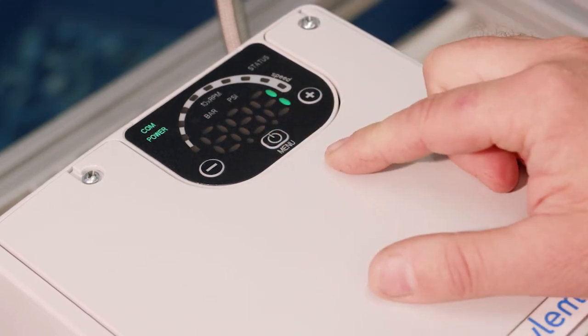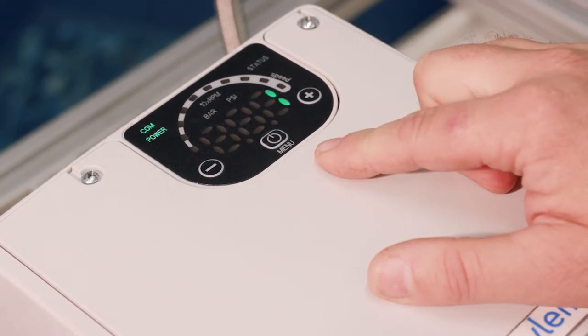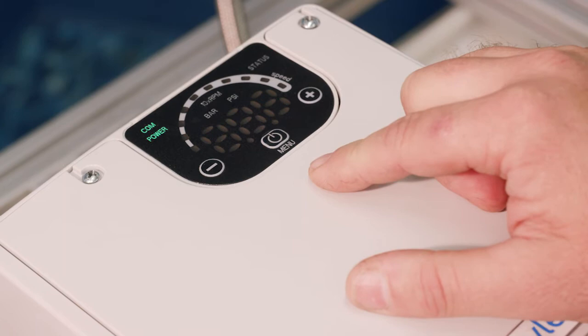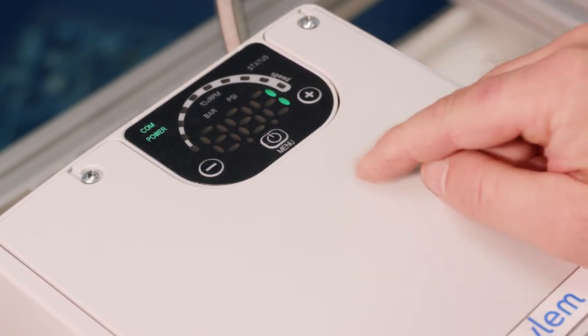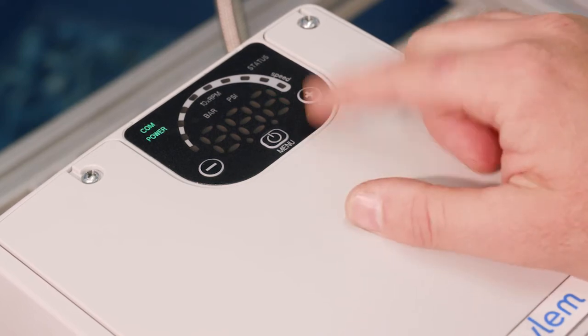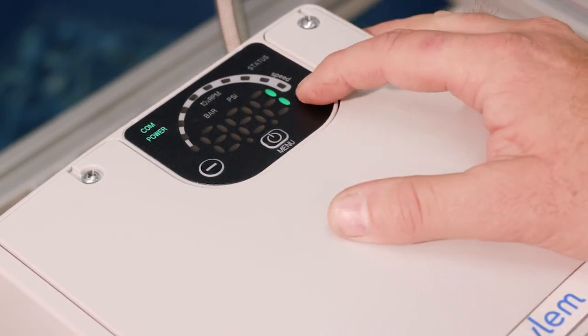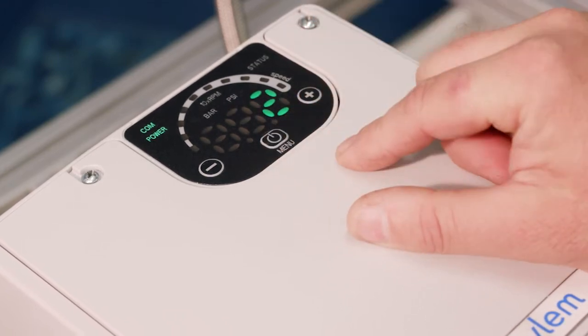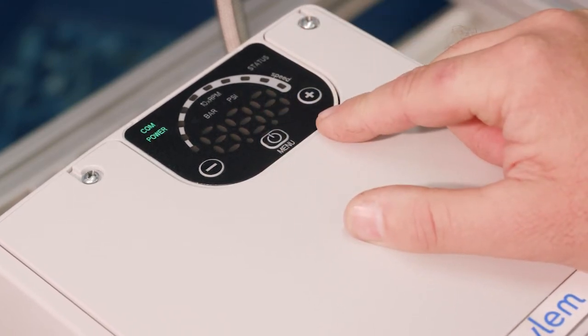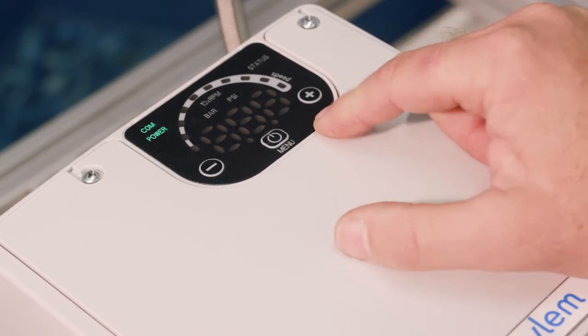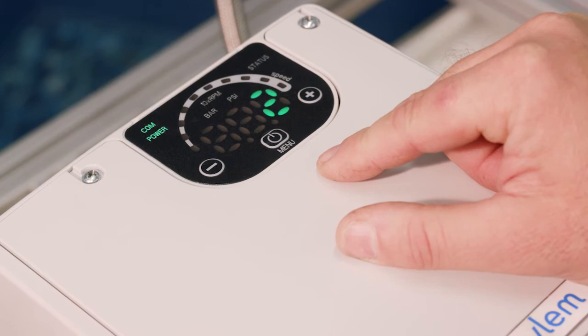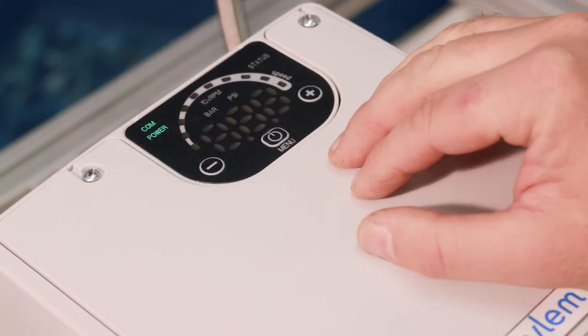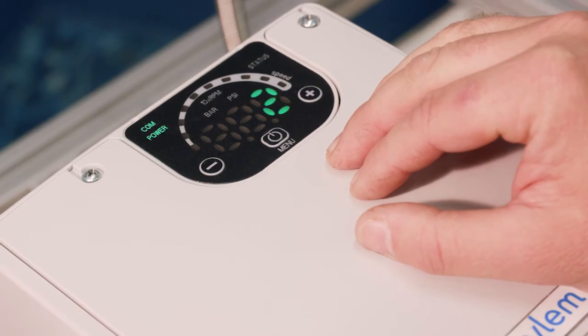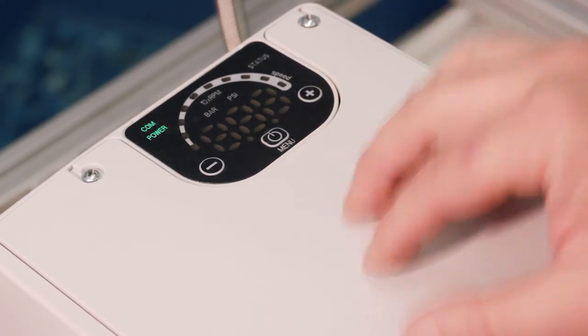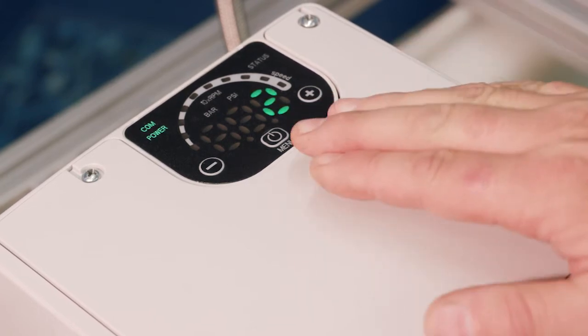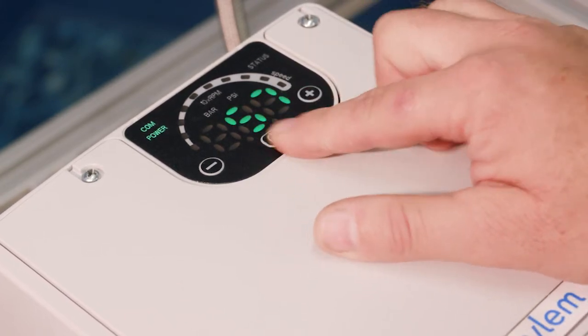And 55 says your address, right? So one thing that we have to do is identify pump 1 versus pump 2. So we'll call this pump 1. So we're good there. 56 is how many units do you have in your multi-pump system? And we have 2, so we're going to leave that. So really, those are the only 2 multi-pump type parameters, those last 2, in terms of address and how many pumps. So again, we have to do that for both units. So we're good with that.